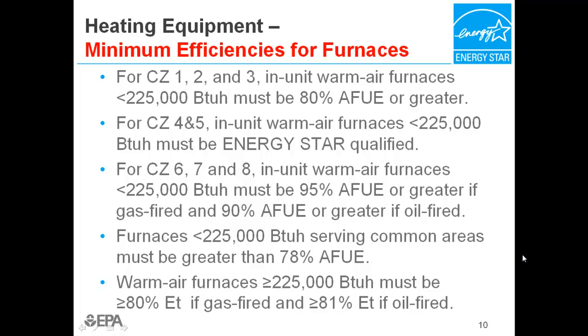In the prescriptive path, warm air furnaces in apartments that are less than 225,000 BTUs per hour in climate zones 1, 2, and 3 don't have to be Energy Star qualified, but they have to be at least 80% AFUE. Warm air furnaces in apartments in climate zones 4 and 5 have to be Energy Star qualified. If in climate zones 6, 7, or 8, they have to exceed Energy Star criteria due to their higher heating loads. If gas-fired, they need to be 95% AFUE or greater, and 90% AFUE or greater if oil-fired.